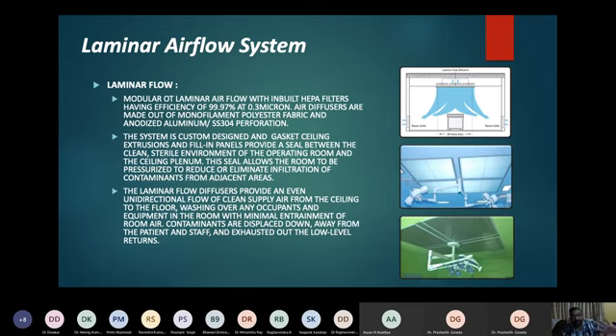Raghavendra and his team were taken through the air portion some time back, but laminar flow is the key component in the modular operation theater. The modular operation theater airflow is inbuilt with a HEPA filter. The filter has an efficiency of 99.97 percent at 0.3 micron. HEPA means high efficiency particulate air, which is the standard for blocking particles.